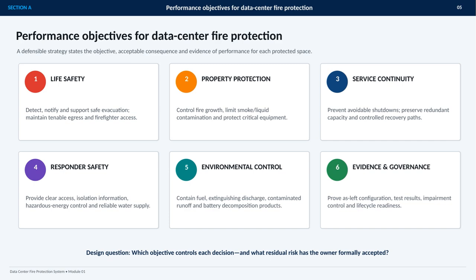Third is service continuity. The strategy should prevent avoidable shutdowns, preserve redundant capacity, and provide controlled recovery paths. The remaining objectives broaden the risk picture. Responder safety requires clear access, isolation information, hazardous energy control, and a reliable water supply. Environmental control addresses fuel, extinguishing discharge, contaminated runoff, and battery decomposition products. Finally, evidence and governance require proof of the as-left configuration, test results, impairment control, and lifecycle readiness.